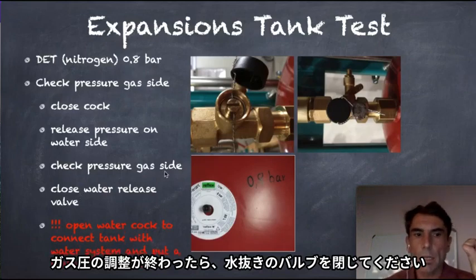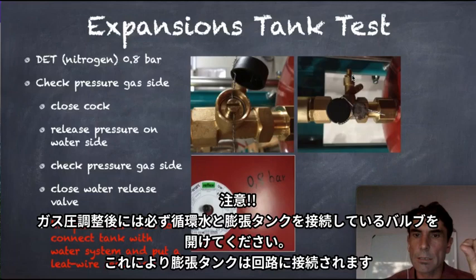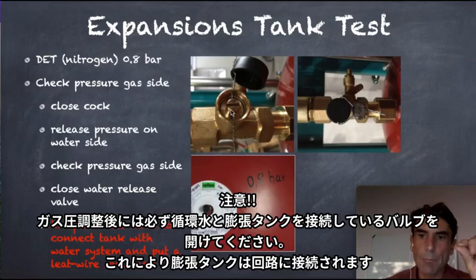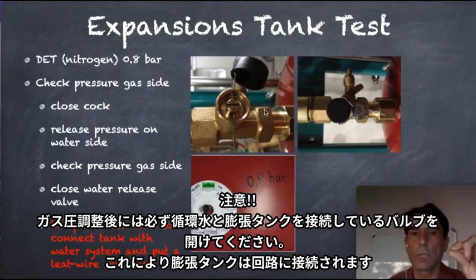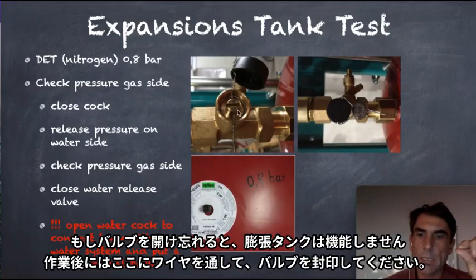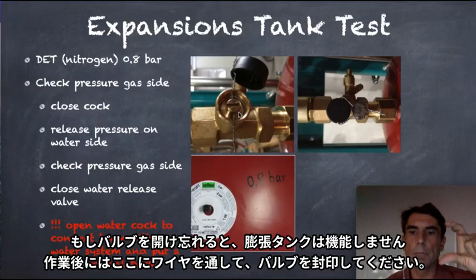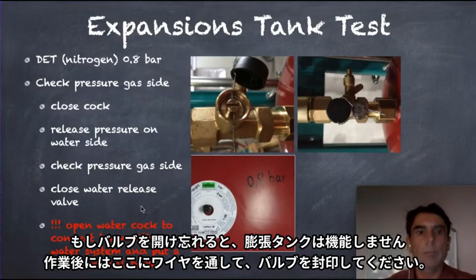Okay, after releasing the pressure and checking the pressure, we close the valve here again. And important, before you go back in operation, the valve here must be opened again, so that we connect the expansion tank to the HTU or to the other water cycle which is connected. If this is still closed, we will not have the balance or the compensation of pressure change through temperature. Very important. And for sure, put the wire seal back in again, so that we make sure this stays open and nobody will change it.